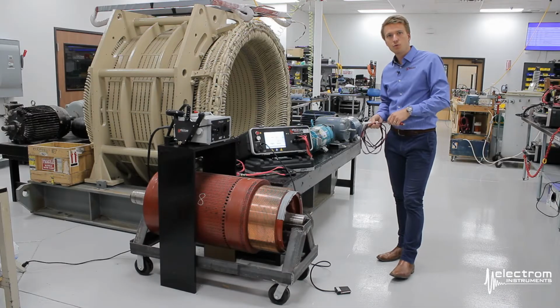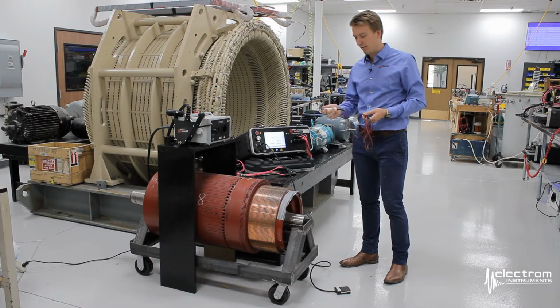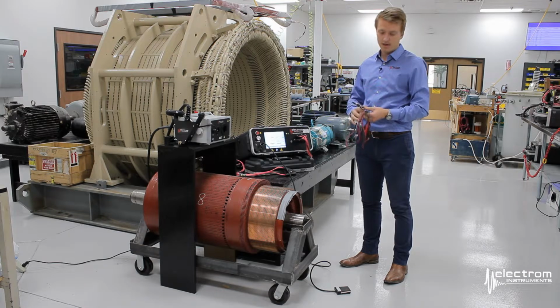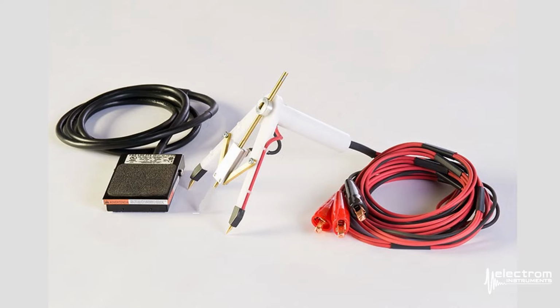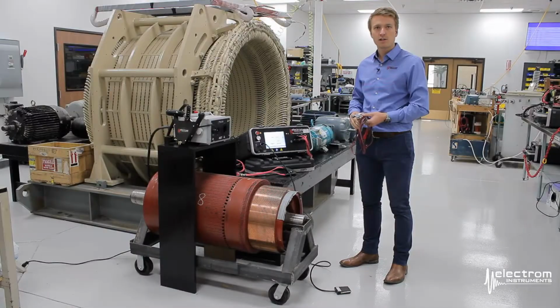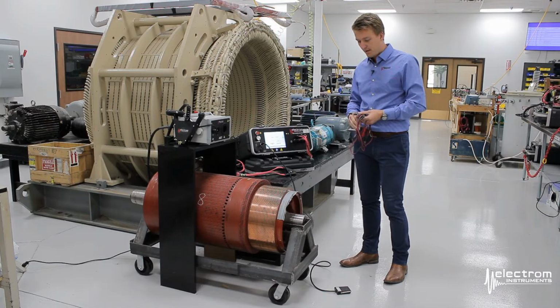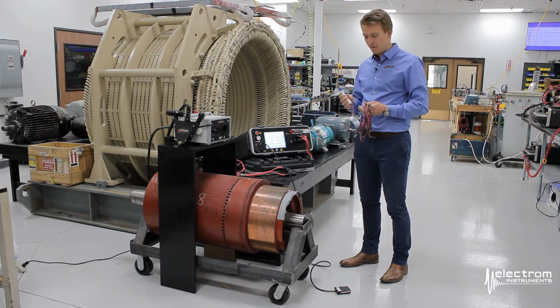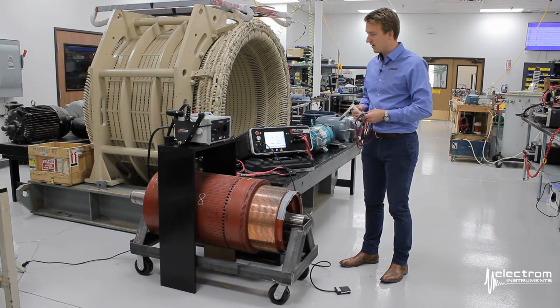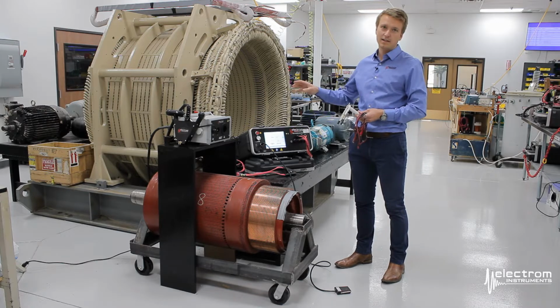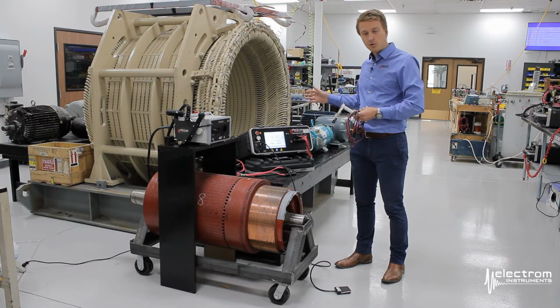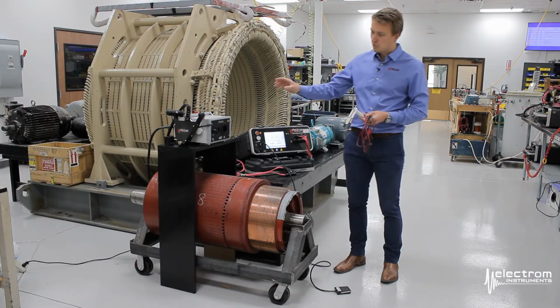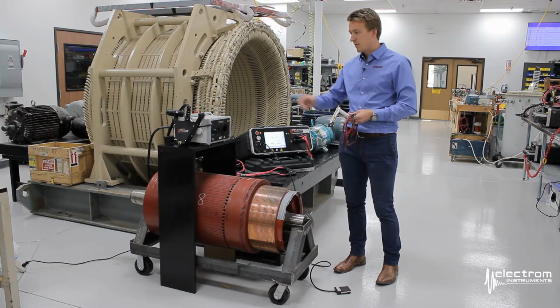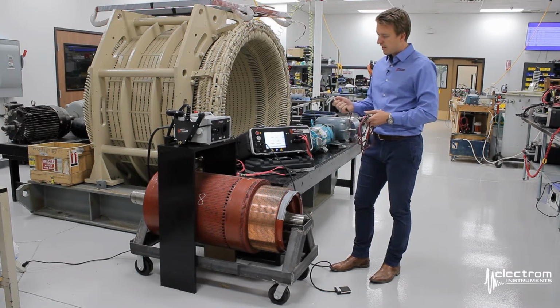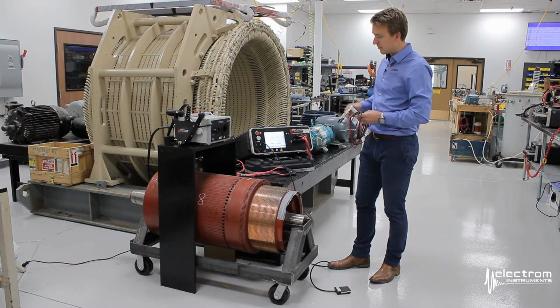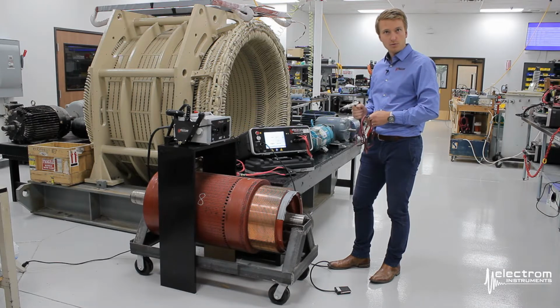As an alternative to the ABT, the ATF-11 or Armature Test Fixture could be a simpler and lower cost option to get surge tests done on a DC armature. The main difference between this and the ABT is that instead of transforming the, relatively speaking, high voltage, low current from the iTIG into lower voltage and high current with a 4-wire probe set, we're now just using the, let's call it, standard output of the instrument with a 2-wire probe set.